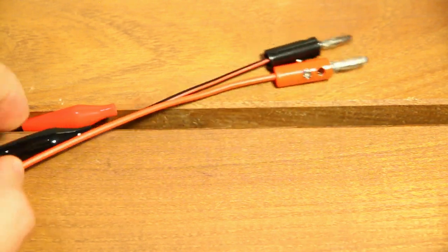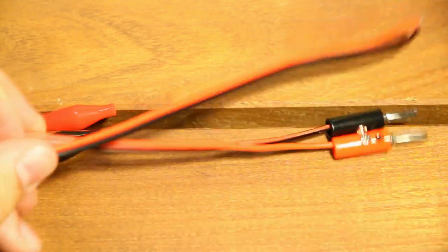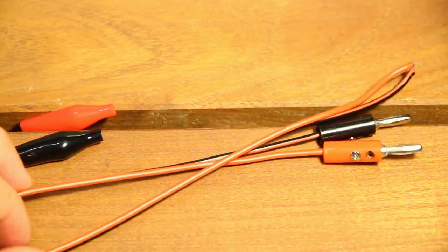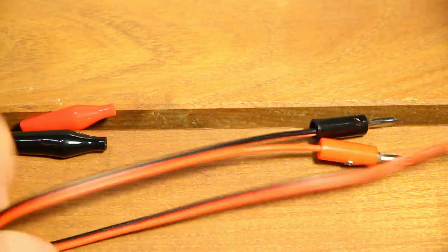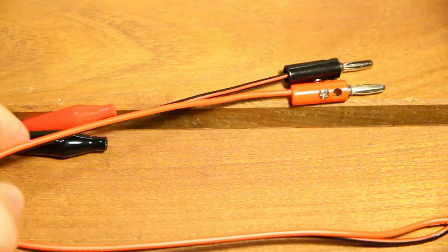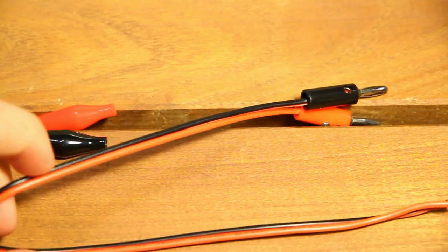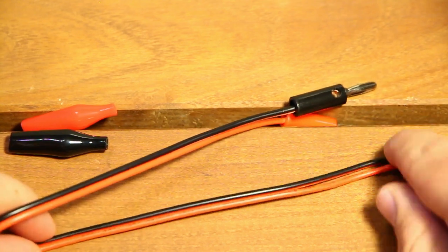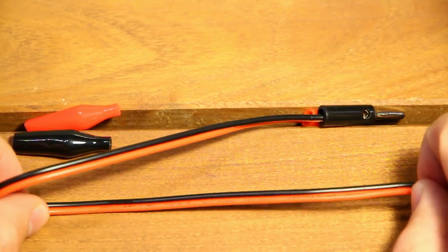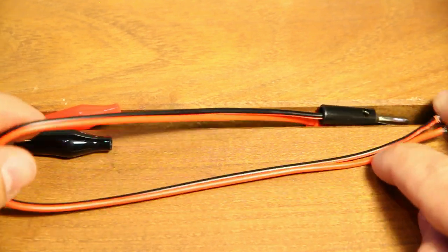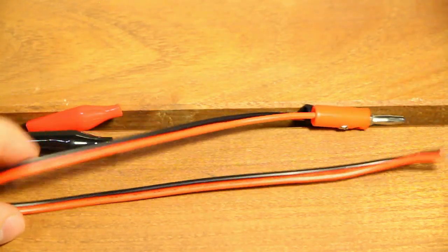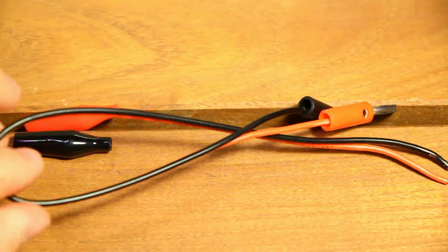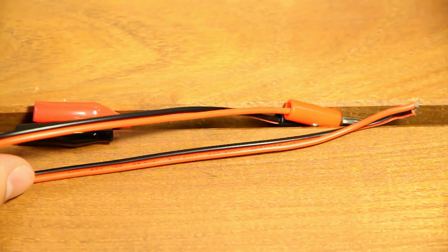This wire is really not sufficient for this application. And you should use it max up to 5 amps. Anything above that I would recommend using a different load wire. So these are definitely not adequate for this application. And you have to throw them out and use something else.